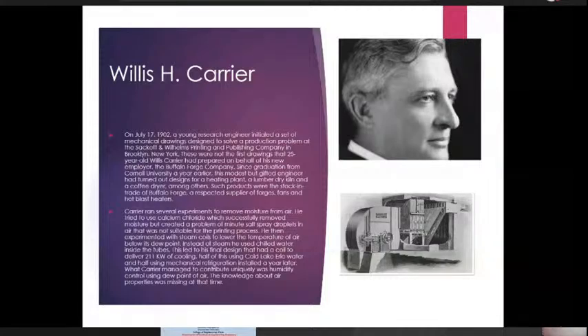So like any engineer, he started by looking at the chemical means of removing moisture. He looked at calcium chloride, and he found that calcium chloride does remove moisture, but it creates another problem: salt spray droplets are added to the air, and that wasn't suitable for the printing process. Then he experimented with steam coils to lower the temperature of air below its dew point. Instead of putting steam through the coils, he used chilled water through those heat exchangers. This led to his final design, a coil to deliver 211 kilowatts of cooling, half of which was using cold lake water and half using mechanical refrigeration installed a year later.